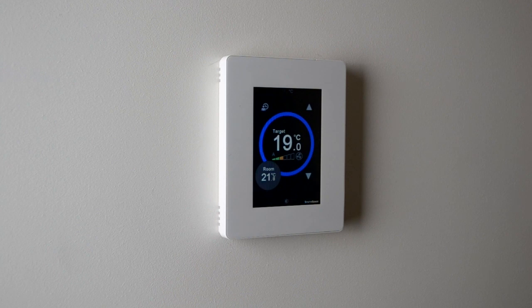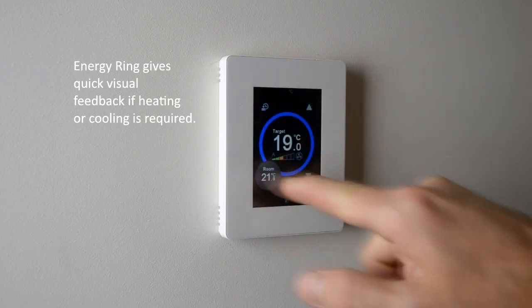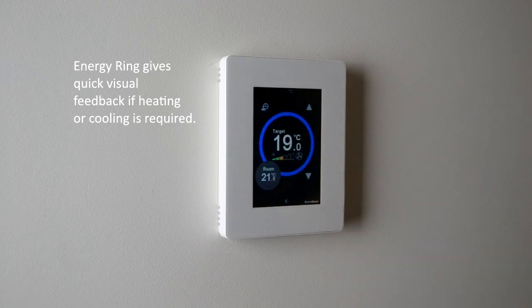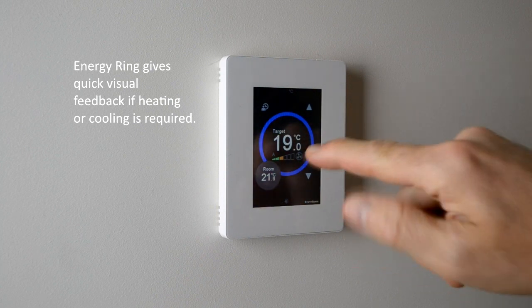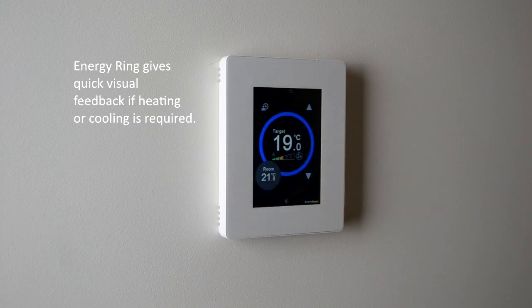What we see here is an energy ring which illustrates if there is a heating or cooling demand. At the moment it shows a blue ring which indicates that there is a cooling demand, because the temperature target is 19 degrees and room temperature is 21.8 degrees.